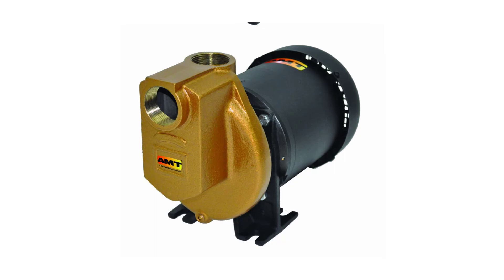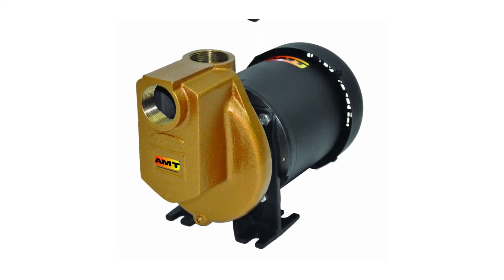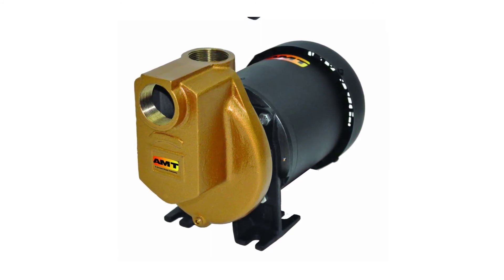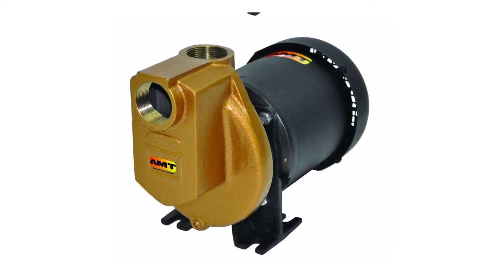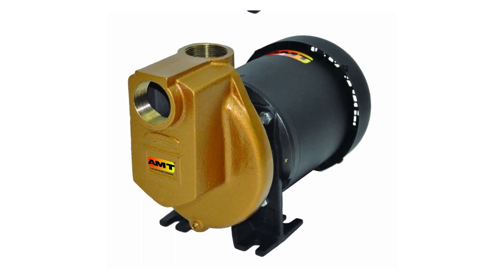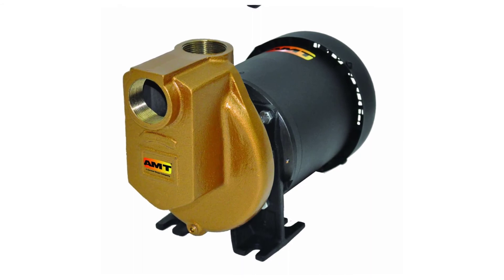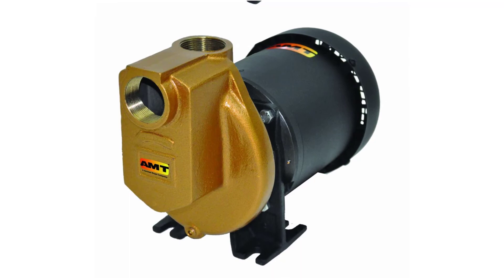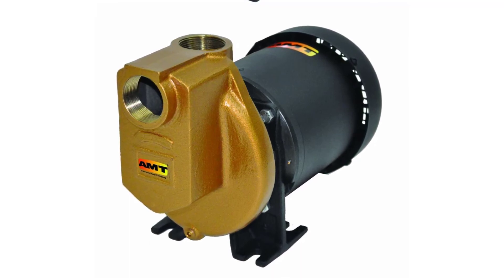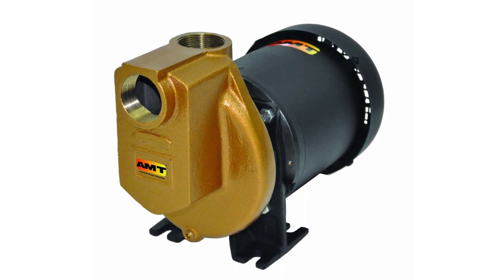AMT Self-Priming Bronze Centrifugal Pump. Designed for chemical processes, wastewater treatment, and pumping agricultural fertilizers and fumigants. Handles liquids with specific gravities up to 1.1 and viscosities to 100 SSU. Cast bronze construction, 300 series stainless steel self-cleaning semi-open impeller, Viton mechanical seal, dual volute design. Max flow 132 GPM, max head 63 feet, self-priming to 6 feet. 1/2 HP, totally enclosed fan-cooled (TEFC), single phase, 115/230 VAC 60 Hz, 56 J-Frame motors.